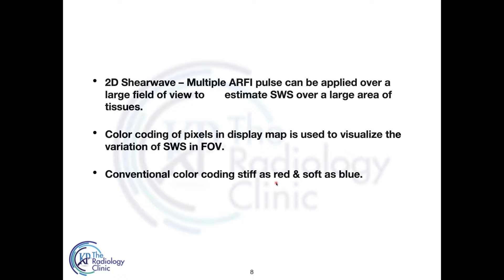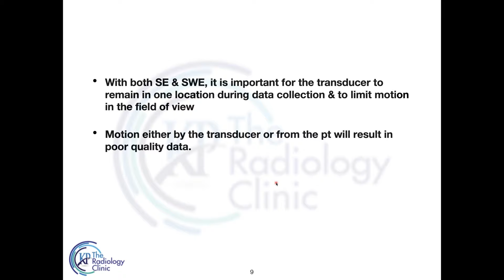With both strain elastography and shear wave elastography, it is important for the transducer to remain in one location during the data collection to limit motion in the field of view. The motion, either by the transducer or from the patient, will result in poor quality of the data.